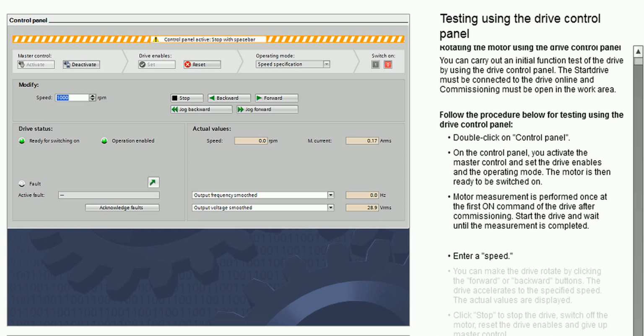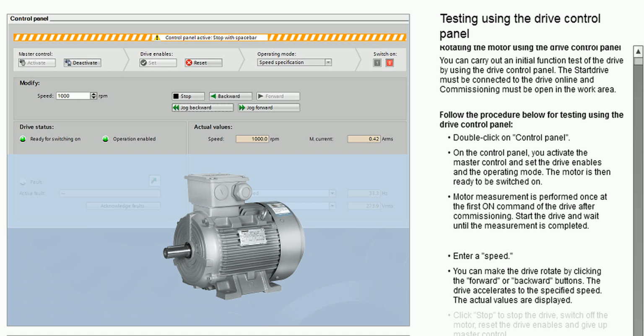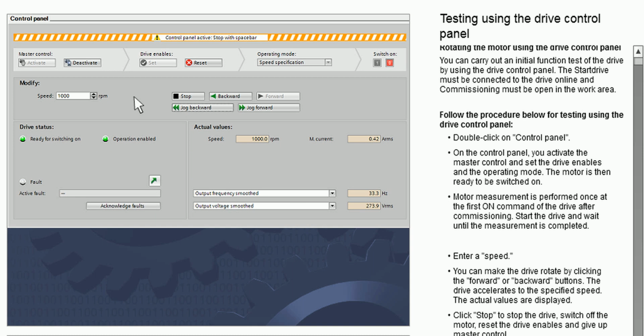Observe the safety instructions in the manual before you make the motor rotate. Enter a speed. You can make the drive rotate by clicking the forward or backward buttons. The drive accelerates to the specified speed. The actual values are displayed. Click Stop to stop the drive, switch off the motor, reset the drive enables and give up master control.